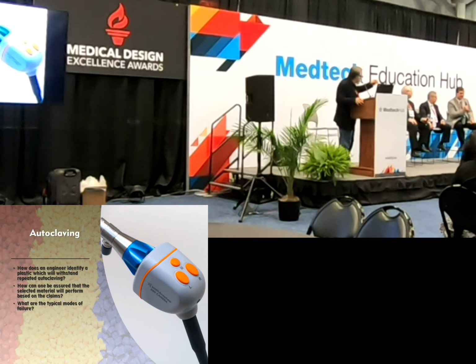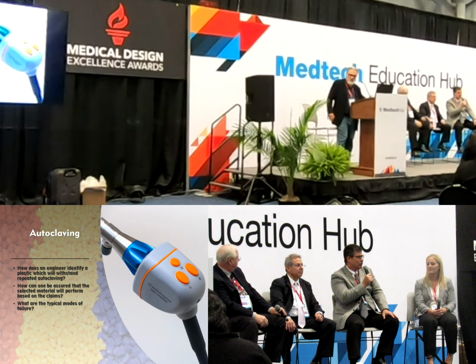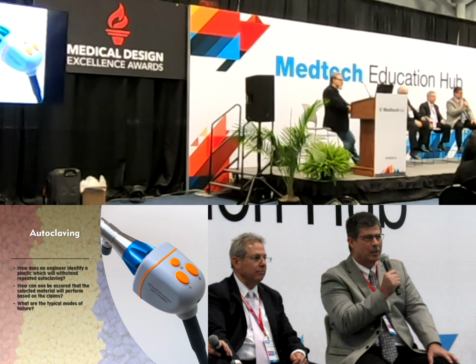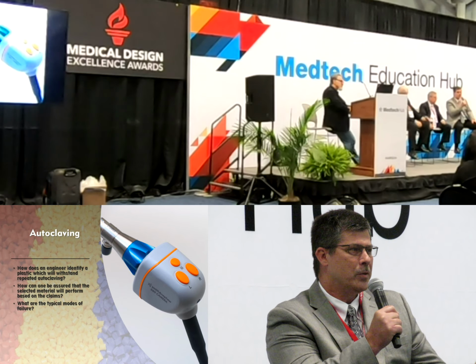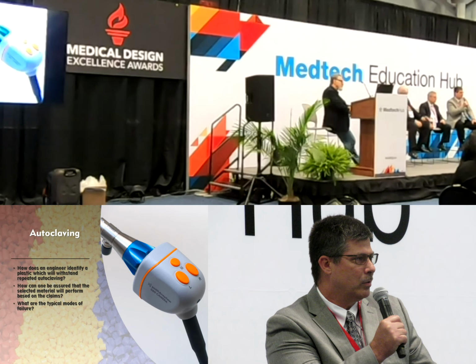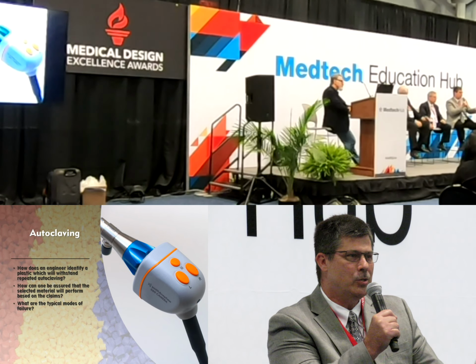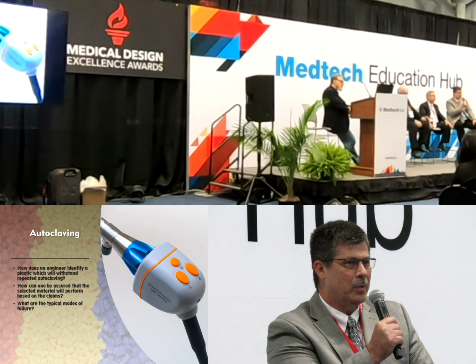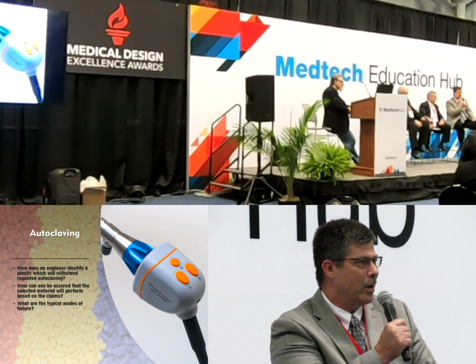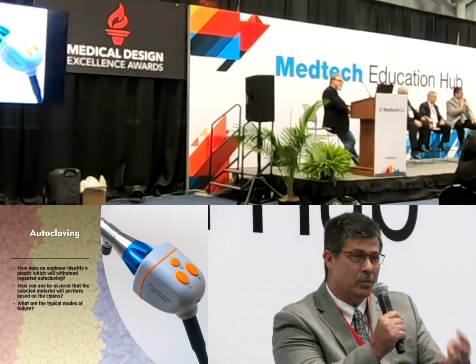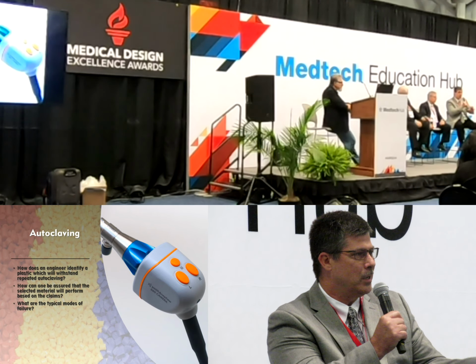Well, first and foremost, there's a smaller number of materials that can truly be exposed to autoclave. There are crystalline materials that have a higher crystalline melting point that can certainly stand up to these higher temperatures. In the amorphous plastics arena, it's going to be based on the thermal glass transition temperature. We call it Tg. And typically you're going to have to be well above around 150 centigrade or higher to be exposed to the two types of autoclave, which are typically 135C and 121C. And that limits the number of materials you can look at.